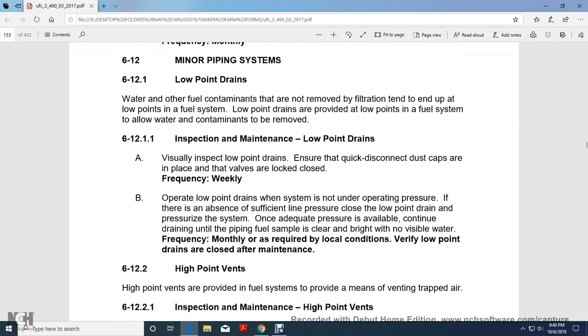6.12 Minor piping system. Low point drains. Water and other fuel contaminants that are not removed by filtration tend to end up at the low points of the fuel system. Low point drains are provided at the low points of the fuel system to allow the water and contaminants to be removed. Inspection maintenance for low point drains: visually inspect low point drains to ensure the quick disconnect dust caps are in place and the valves are locked and closed, weekly. Operate the low point drain when the system is not under operating pressure, in the absence of sufficient line pressure.